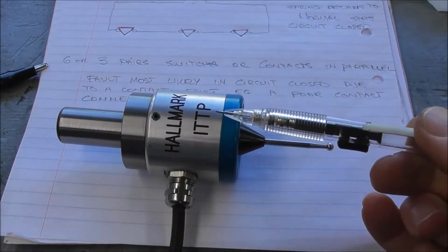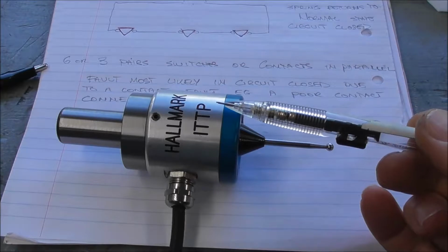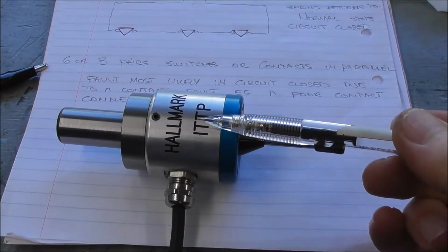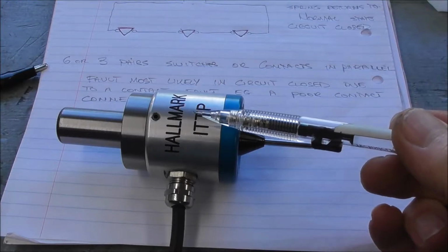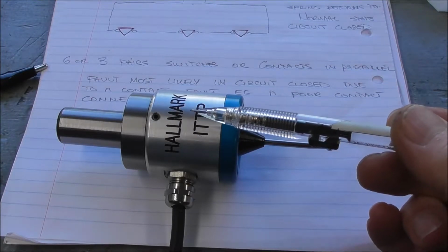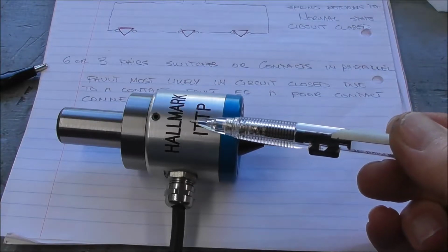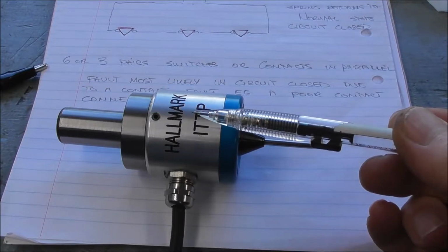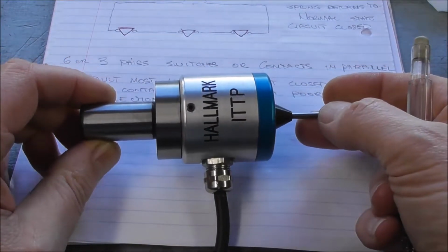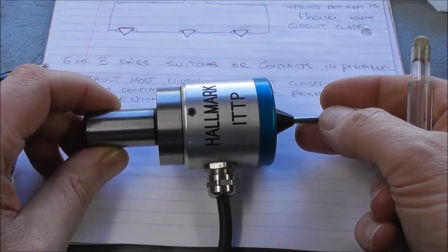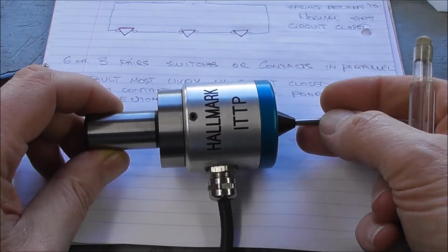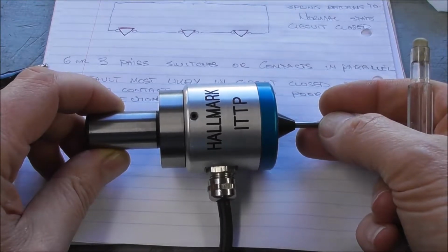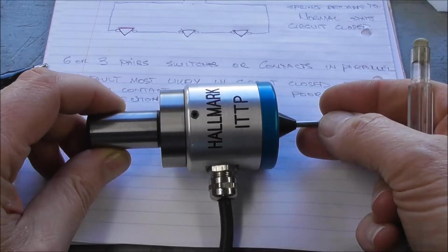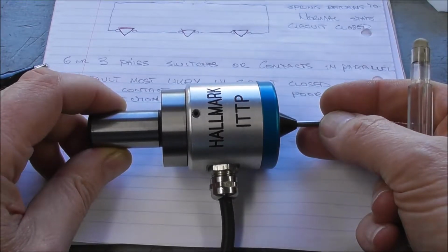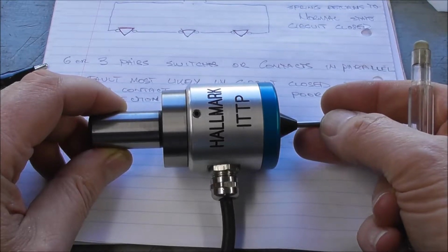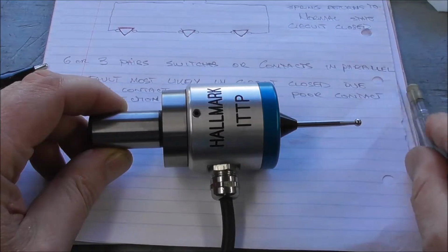Now, if there's a fault in the circuit due to it being open when it should be closed, in other words, the probe tip is not touching the work, the spring returns the contacts to their normal state of circuit closed, but in actual fact there is no current running through the probe, there is no closed circuit, then it could be due to a break in the circuit within the body of the probe, a dry solder joint or a poor connection of a pogo contacting on the balls and so on. And if you look at the section in part 2, it'll show you the electrical circuit components, how they fit together, the type of things that could be wrong and could be checked to find where that fault is and correct that fault.